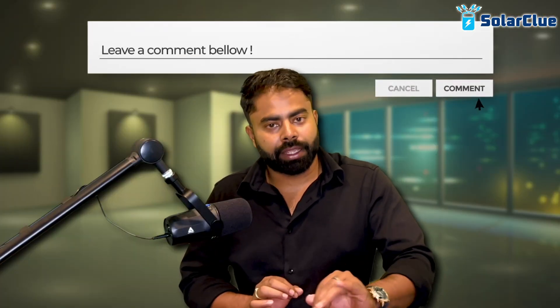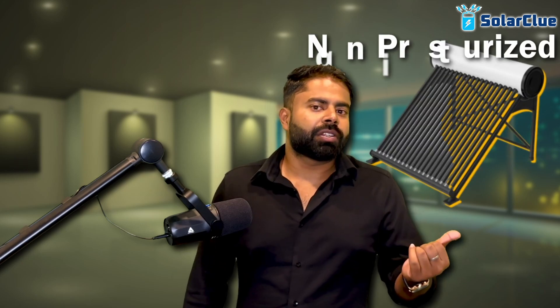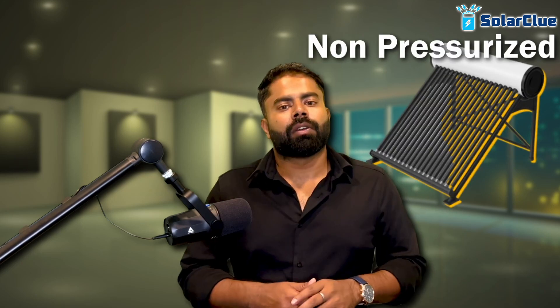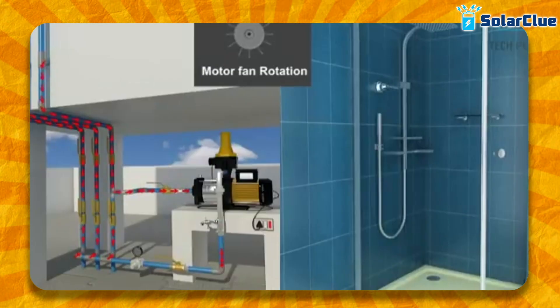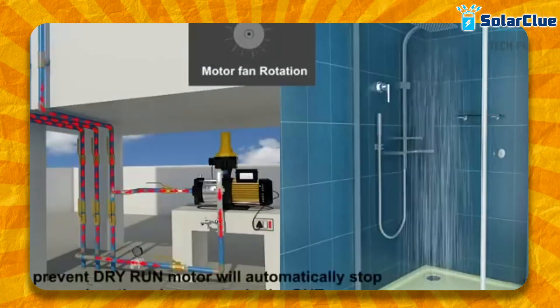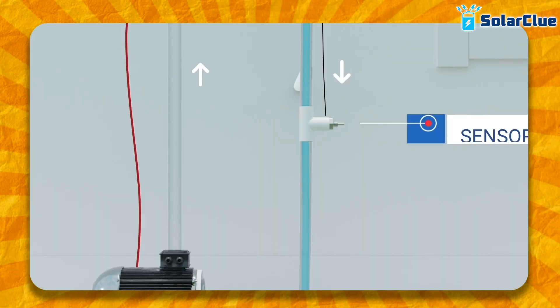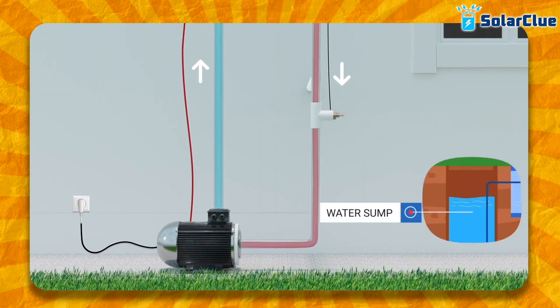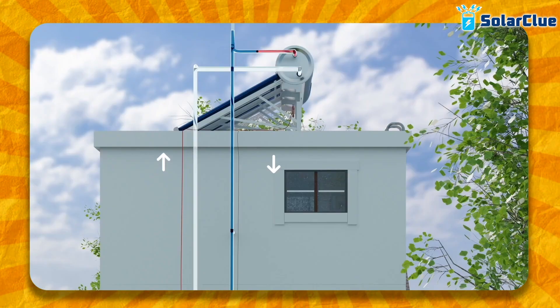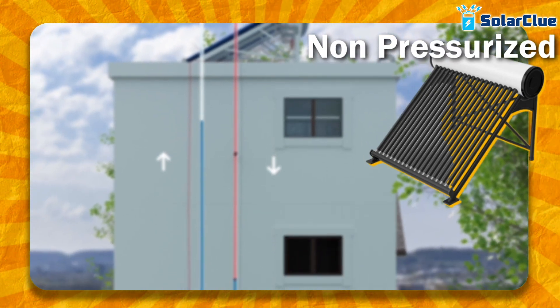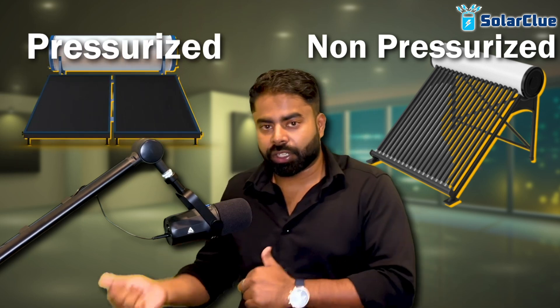Simple logic: buy non-pressurized if you don't have a pressure pump on the terrace; buy pressurized if you do have one. For villa communities with a centralized pumping system that pumps water directly to your bathroom at good pressure, you need a pressurized heater. But if the community pumps water to an underground sump and then to an overhead tank which feeds the bathroom by gravity, you need a non-pressurized heater.